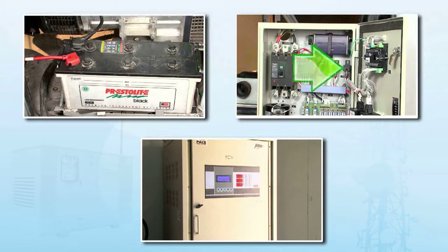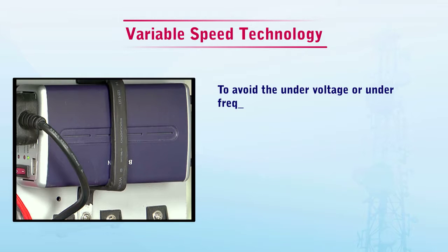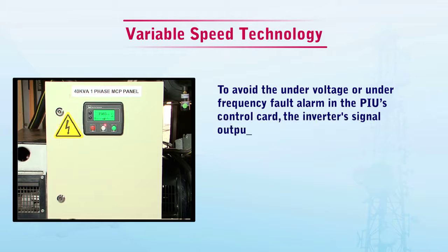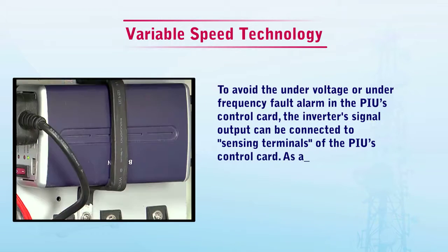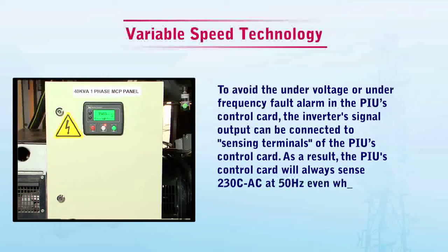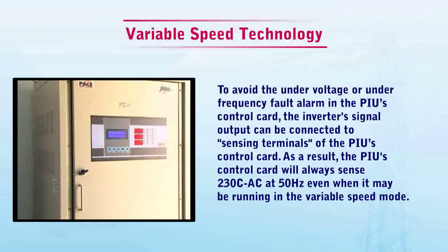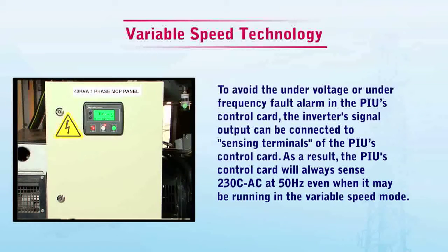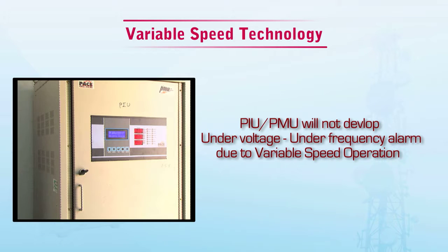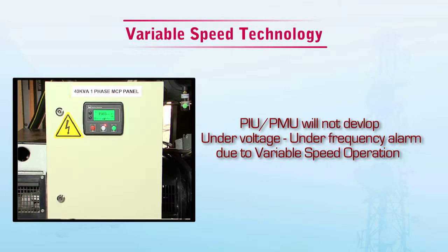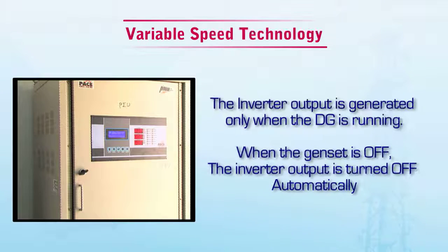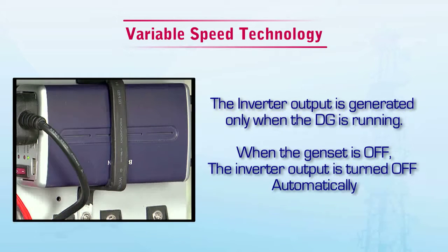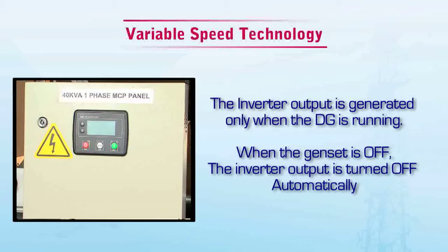This inverter is powered by the genset's 12-volt battery, and it develops 230 volts AC at 50 Hz frequency. To avoid the undervoltage or underfrequency fault alarm in the PIU's control card, the inverter's signal output can be connected to the sensing terminals of the PIU's control card. As a result, the PIU's control card will always sense 230 volts AC at 50 Hz, even when it may be running at the variable speed mode. As a result, the PIU control card will not develop an undervoltage or underfrequency fault alarm due to the variable speed operation. Importantly note that the inverter output is generated only when the DG is running. When the genset is off, the inverter output is turned off automatically.